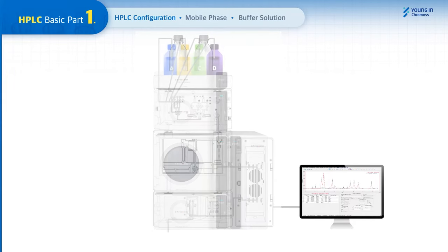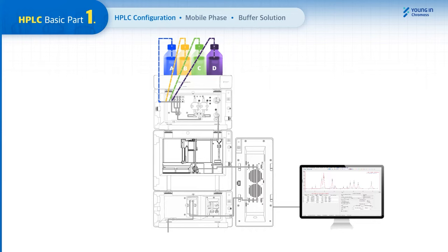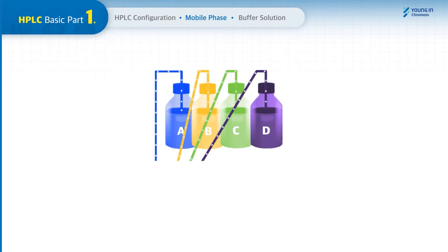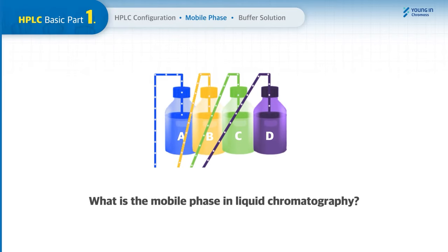The mobile phase is drawn to the pump and passed through a vacuum degassing unit, which removes dissolved gases. The degassed mobile phases are mixed in the right composition rate depending on the application. The injector loads and injects the sample, and the pump delivers the sample to the column with the mobile phases. The samples are separated into individual components through various chemical interactions with the solid phase in the column. The detector then converts the concentration of each component into an electrical signal, and the signals are shown as a chromatogram by the chromatography data system.